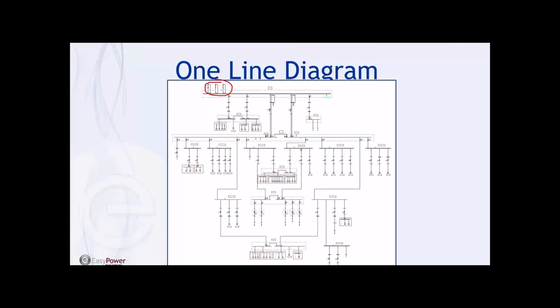Gas turbine, diesel generators — we generate at 13.8 kilovolts, and we have a lot of switchgear. Basically, a lot of power transformers which step up or step down the energy from 13.8 to 480, for instance, to have low voltage. We have two power transformers here to step up the power from 13.8 to 34.5 kV, so we have a lot of distribution at 34.5 kV, and at 34.5 kV we reach different areas of the project.